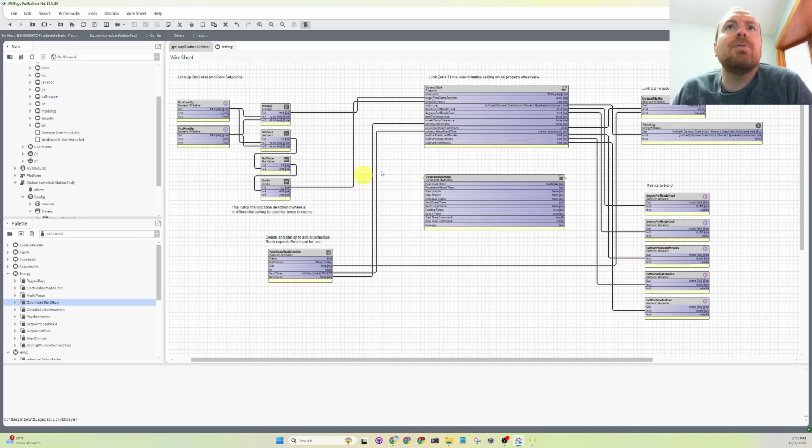One thing to note, I'll demonstrate this on a live system, but we wire in our zone temp, same thing here, the space temp, and they're using outside air temp 2 in their model. Then we always have to wire in a Boolean schedule. The optimal start blocks always require a next time and a next value.